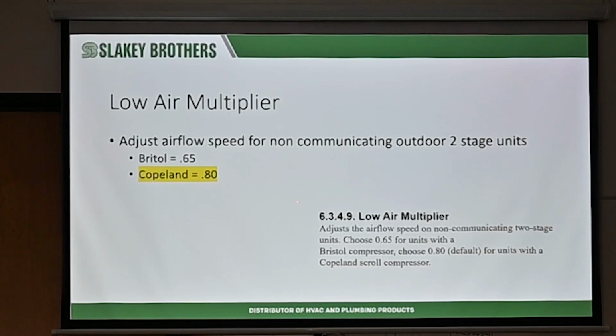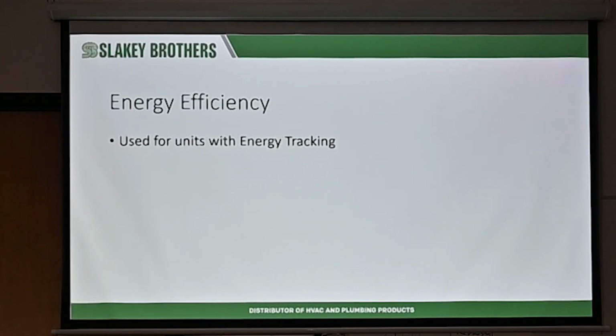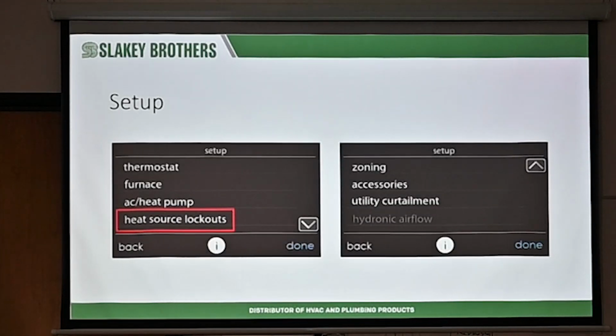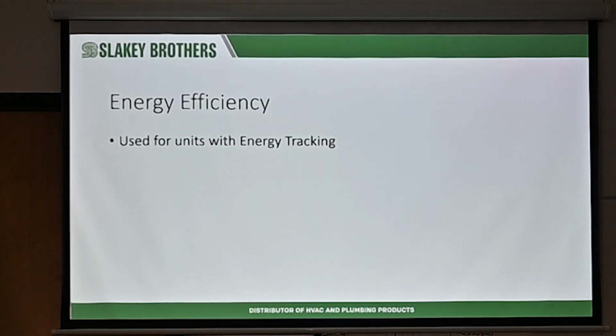This one you don't have to worry about at all. Reason being, pretty much all these Bristol compressors on the older two-stage units, they're all gone. You can't even replace these Bristol compressors, they're obsolete anymore. So the default is Copeland compressors. They come defaulted for 80% of high is how it's set up. So airflow on low stage cooling will be 80% of high stage automatically with the Connex controller. It'll just do it all for you. And all this will be based off of your adjustments in regards to 350 or 400 CFM per ton. It will modulate the low cooling automatically for you with the Copeland two-stage. Again, that's only for the variable speed stuff.